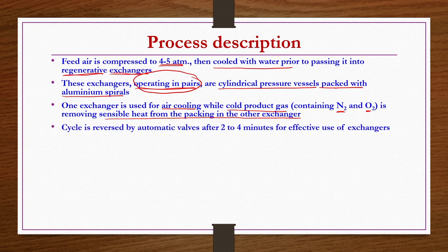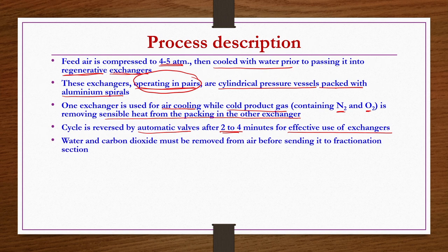These cycles are reversed by automatic valves after 2 to 4 minutes depending on the plant, for effective use of exchangers. First, exchanger 1 is used for air cooling and exchanger 2 is used for removing sensible heat from the packing material. After reversing, exchanger 1 is used for removing sensible heat and exchanger 2 is used for air cooling, since both have aluminum spiral packing and are designed this way.